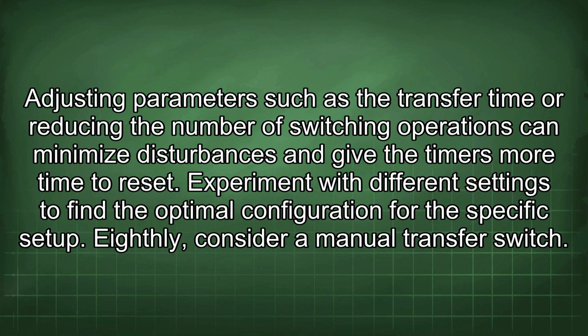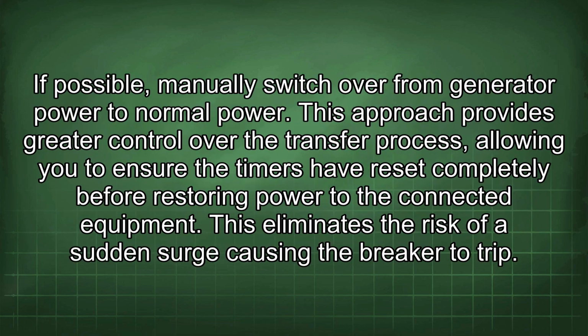Eighthly, consider a manual transfer switch. If possible, manually switch over from generator power to normal power. This approach provides greater control over the transfer process, allowing you to ensure the timers have reset completely before restoring power to the connected equipment. This eliminates the risk of a sudden surge causing the breaker to trip.